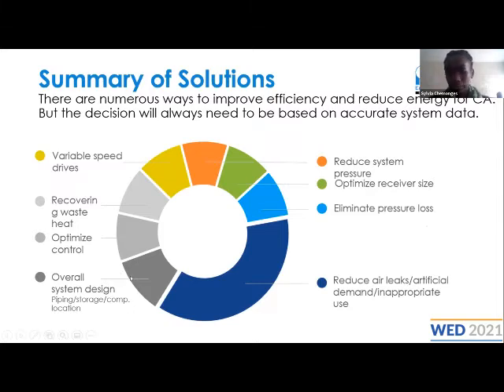Another thing, in summary, would be to consider using a good overall design of your system. So looking at the supply side, you look at which compressor do I need? Is my demand varying or is it fixed? If my demand is varying, consider using a VSD. If my demand is fixed, then consider using a fixed speed compressor. We look at the size of piping. How much flow rate am I supplying from the compressor? What pipe size is required for this particular flow rate to minimize losses? The filters and the dryers that we select, am I able to have minimum pressure drop across these equipment? So it's very important to consider the overall design of your system when trying to improve it.